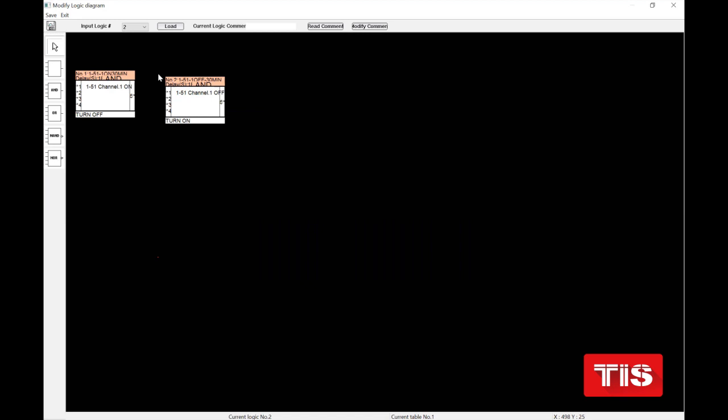Okay, one of our friends asks, is there an easy way to see which logic you already programmed? For example, if you already put some things in an ES and some in a logic, is there an overview of the programming? No, these two devices cannot see each other's programming. You need to know about them and program them. For example, if you program on the ES, if detect motion, turn on the light. And on the logic program, if detect motion, turn off the light.